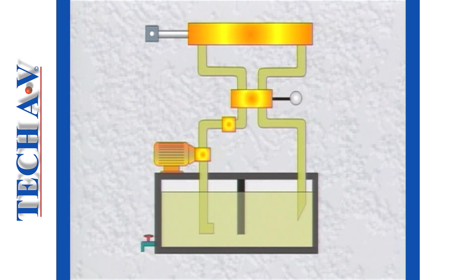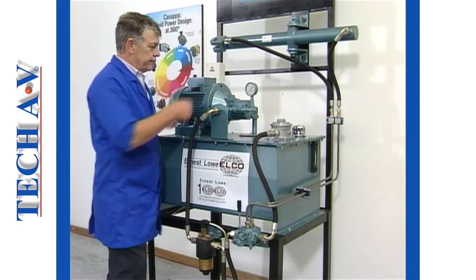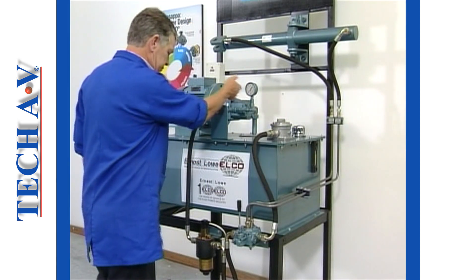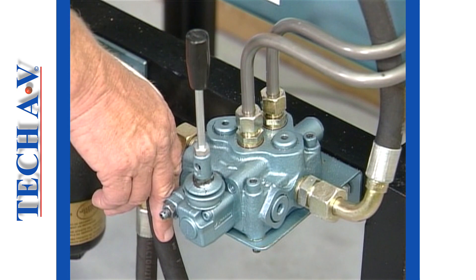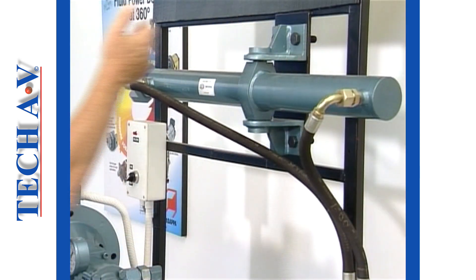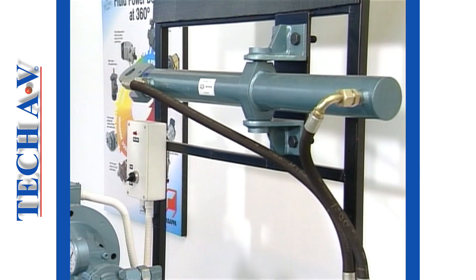High temperatures in any of the major components indicate a friction-related problem that, in turn, indicates wear in the internal components. With your hand, carefully touch the casings of the pump, the pressure relief valve, the direction control valve, and the actuator. If any component proves to be excessively hot, then make a note of this on your report.